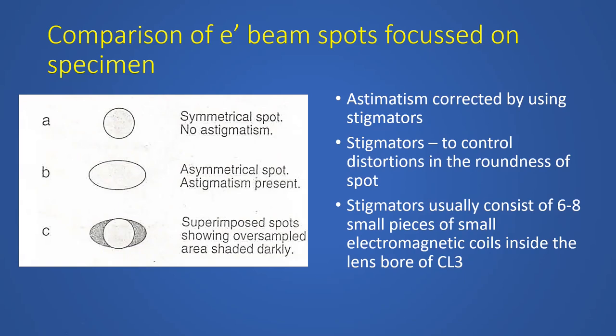For obtaining a good image in an SEM, especially at very high magnifications and high resolutions, you need to correct for astigmatism. This is a very common aberration and common problem. Unless you use proper stigmation, you won't get a good image. So B is the kind of spot that you get for an astigmatic condition. It's an asymmetrical spot, right? So we need to compensate for this using stigmators.